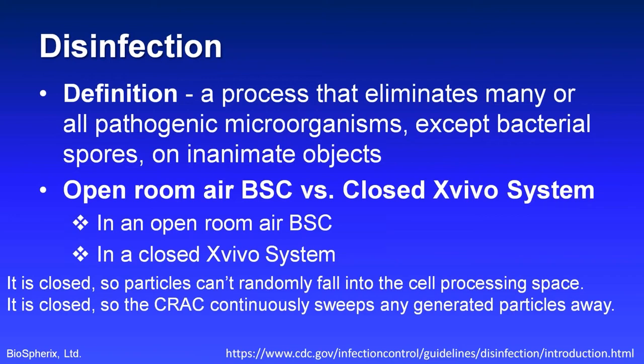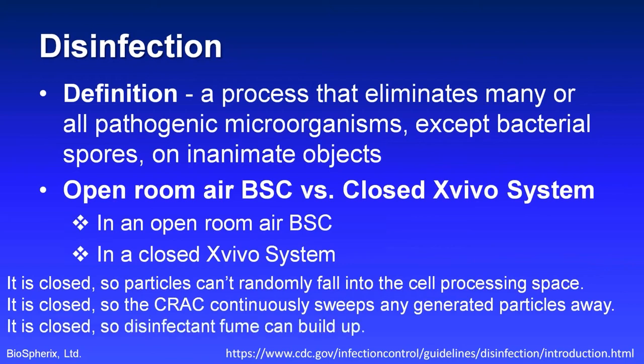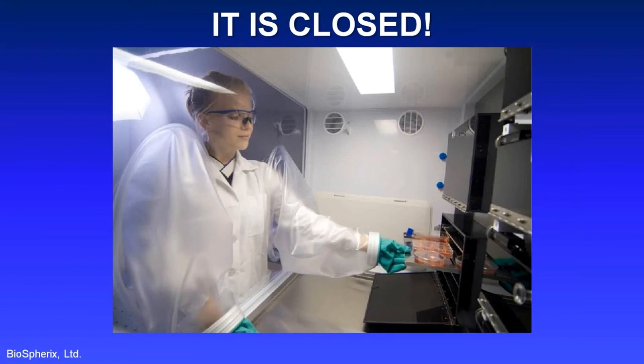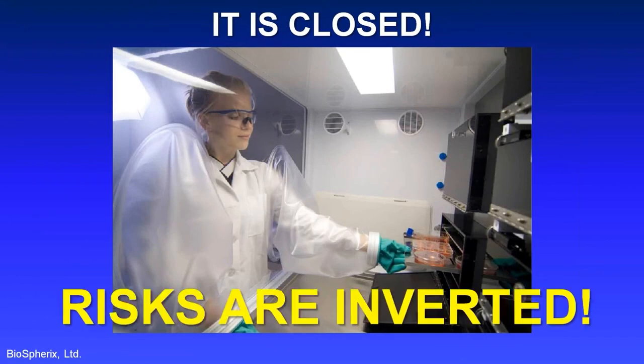It is closed, so the airflow continuously sweeps any generated particles away. And it is closed, so disinfectant fumes can build up. Therefore, those risks are inverted as compared to a room-air BSC.